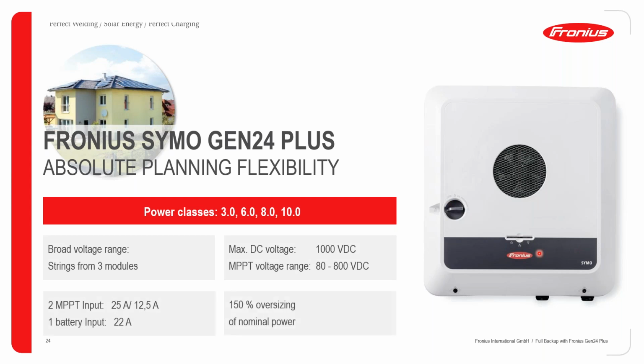So with the Gen24 Plus, you can achieve really good system planning. And this is because we have a wide range of power classes available. Okay, so with the Gen24 Plus, it starts from 3 kilowatts and it goes all the way up to 10 kilowatts, three-phase. Okay, we allow for very broad voltage range. So our voltage range can start from as low as 3 modules and build up. Okay, so the maximum DC voltage you can have per string is 1000 volts DC with the Gen24 Plus.